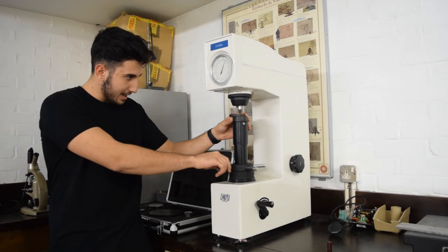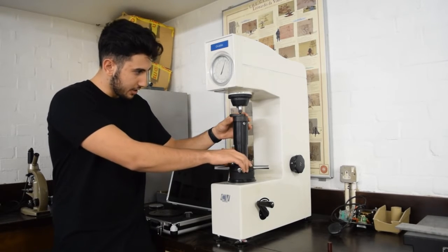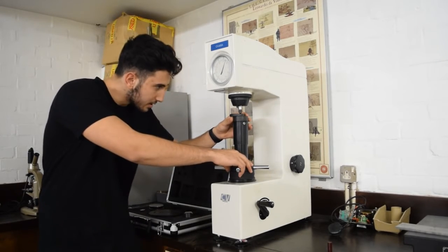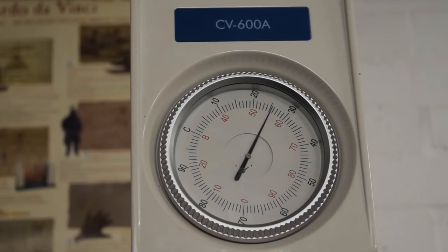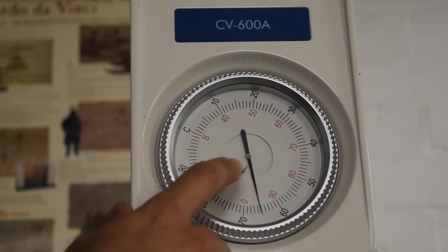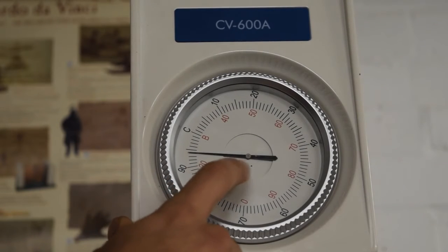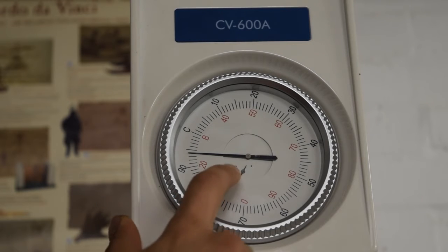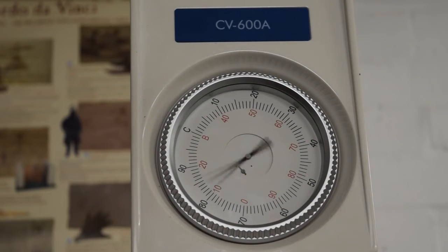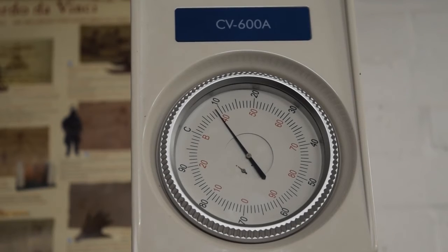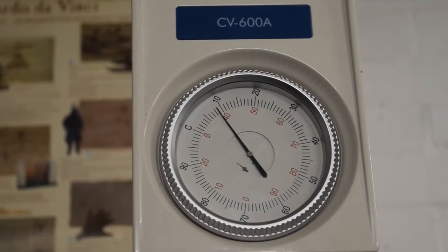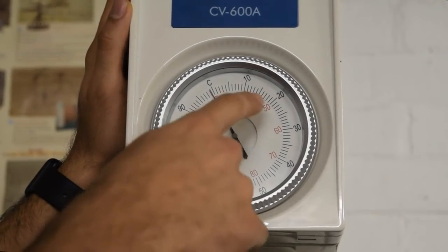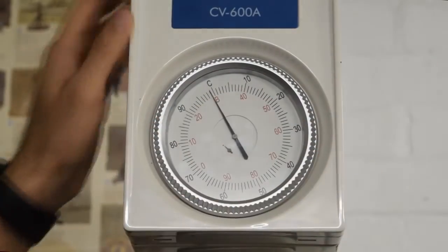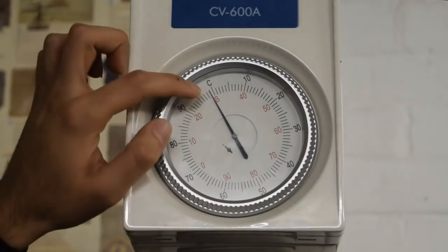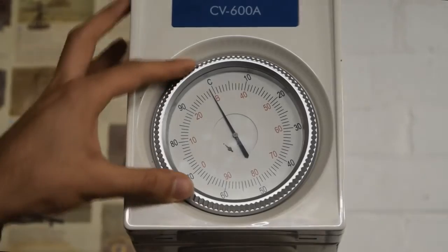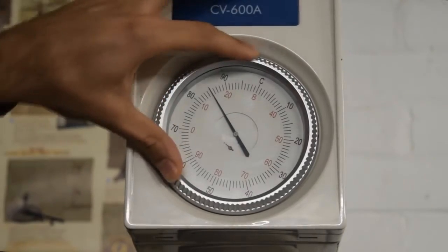Find a nice flat spot on the indenter and just let it touch the surface of the test material. By turning this feed handle, we'll apply the minor load by allowing the small needle to touch the red dot. So once that's there, we've applied the minor load. As we're using the B scale indenter, we have to look at the inside reading of the dials. So we want to position the big needle so it hits 0 on the red scale.